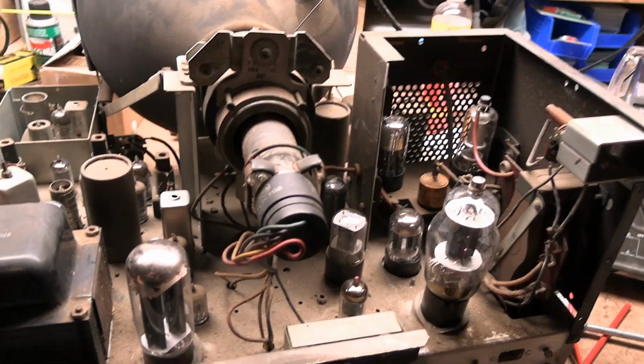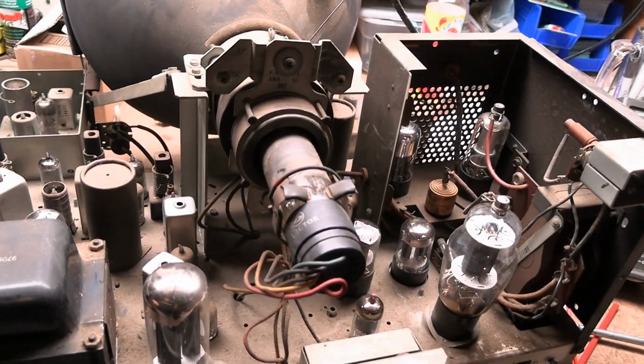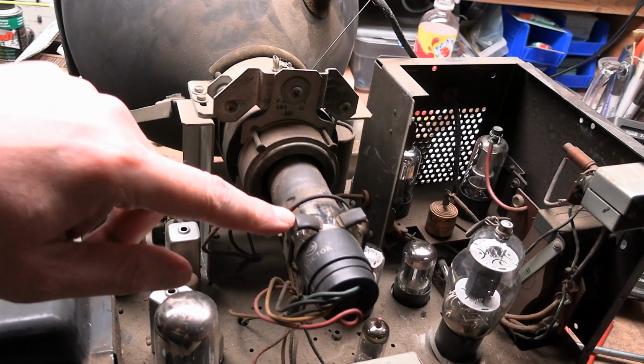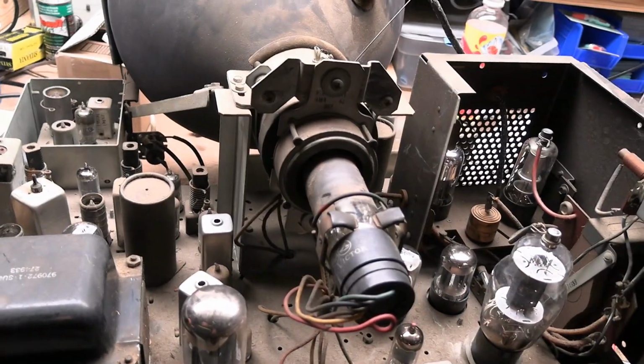Something's not right. I think what's happening is the electrons are hitting the side or some internal gun element. It could be there's a problem with the gun itself and it's damaged, or maybe this ion trap magnet is on the wrong way. I need to flip it around. I've got to check the service info.